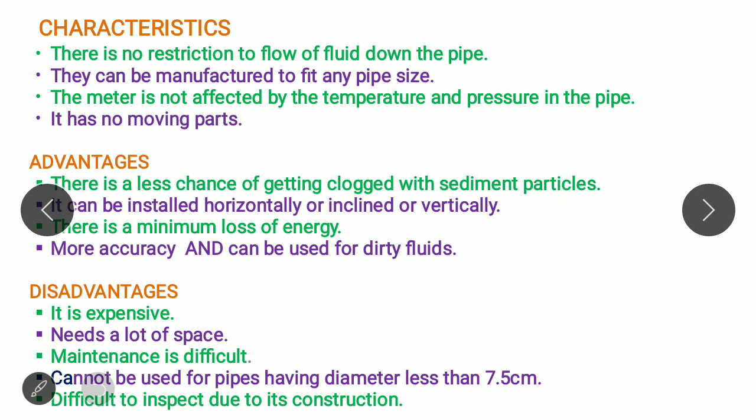The advantage is there is less chance of getting clogged with sedimented particles because the diameter of the pipe is quite large. Moreover, it can be installed horizontally or inclined or vertically and there is minimum loss of energy because there is slow tapering, slow convergence, slow divergence. The loss in energy is minimum. This is the major difference between the Venturi and Orifice meter. It is more accurate and can be used for dirty fluids because there is no clogging.